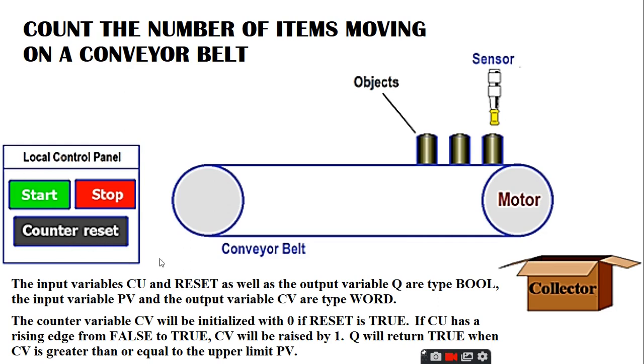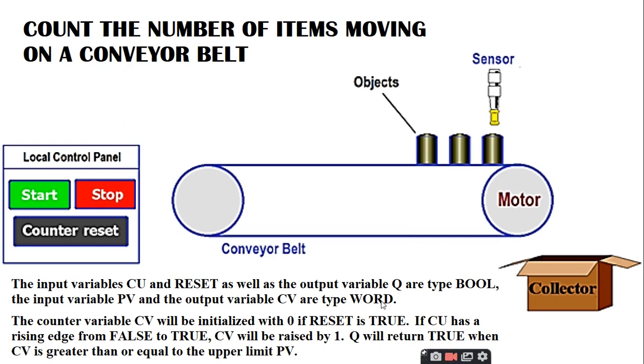We need one counter in CoDeSys to design this particular task. A counter has the input variables CU and RESET as well as the output variable Q. All these three are bool type variables. The input variable PV and output variable CV are of type word. The counter variable CV will be initialized with zero if RESET is true. If CU has a rising edge from false to true, CV will be raised by one. Q will return true when CV is greater than or equal to the upper limit of PV.